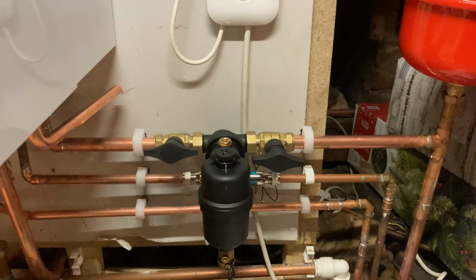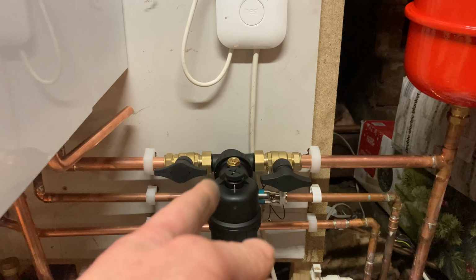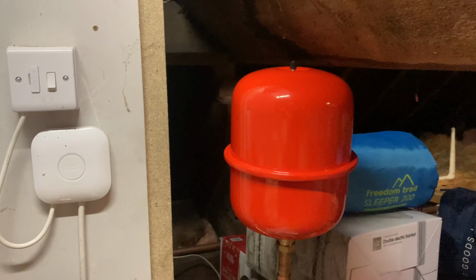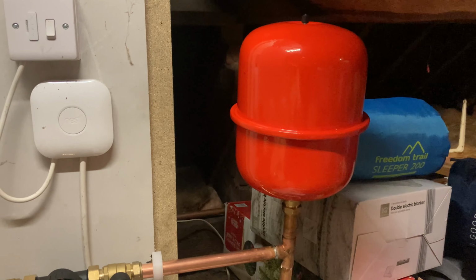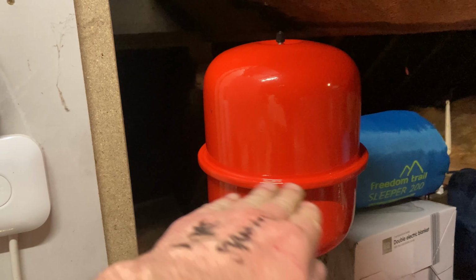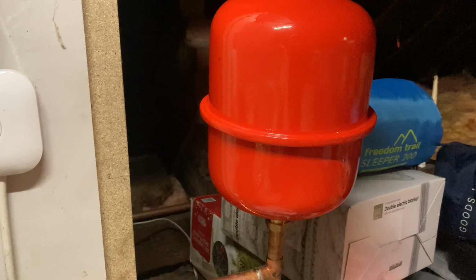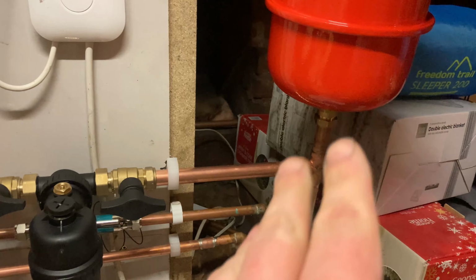Filter. Filter goes in the return to protect the heat exchanger. The vessel goes in the return to protect the diaphragm. The neoprene diaphragm in that will have a better durability being on a colder return temperature.